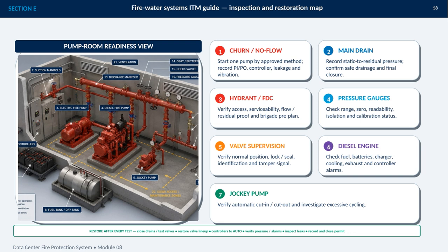For the hydrant or fire department connection, verify access, serviceability, flow, and residual pressure evidence, and the brigade pre-plan. Then examine the pressure gauges for suitable range, zero position, readability, isolation, and calibration status. Valve supervision requires the normal position, lock or seal, identification, and tamper signal to be verified.